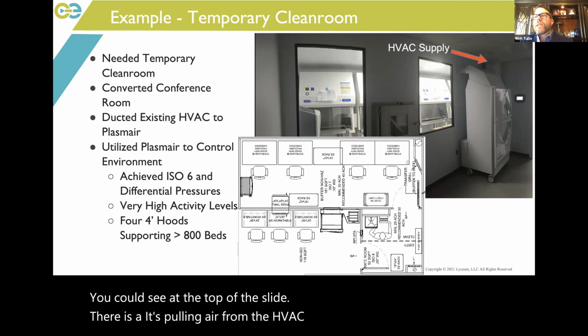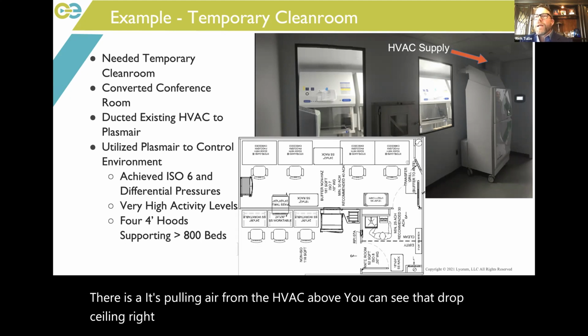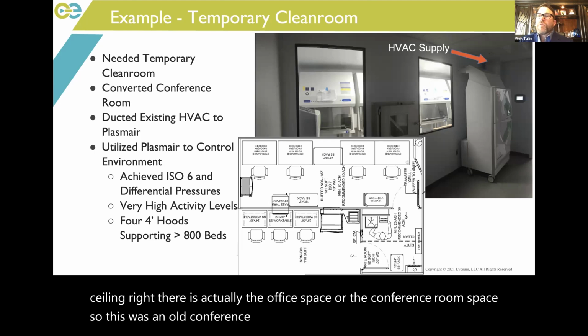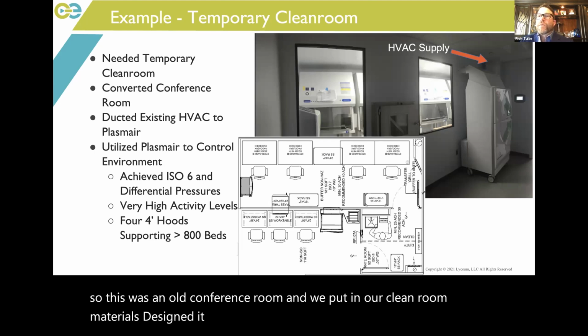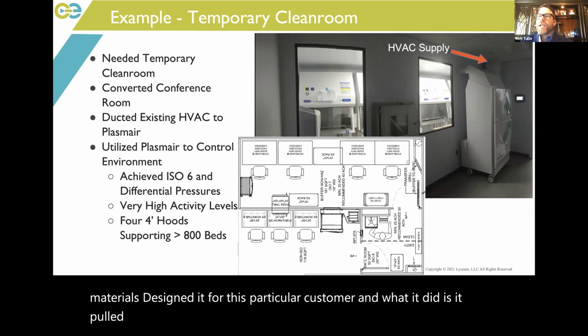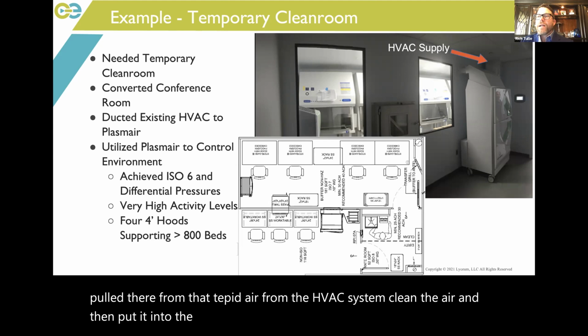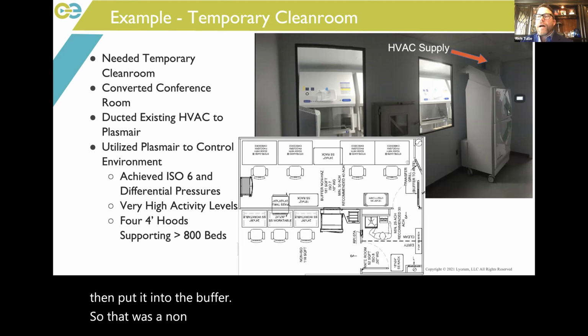And you can see that drop ceiling right there is actually the office space or the conference room space. So this was an old conference room, and we put in our clean room materials and designed it for this particular customer. And what it did is it pulled tepid air from the HVAC system, cleaned the air, and then put it into the buffer. So that was a non-HD buffer, and then across the anteroom, and then out to the workroom.